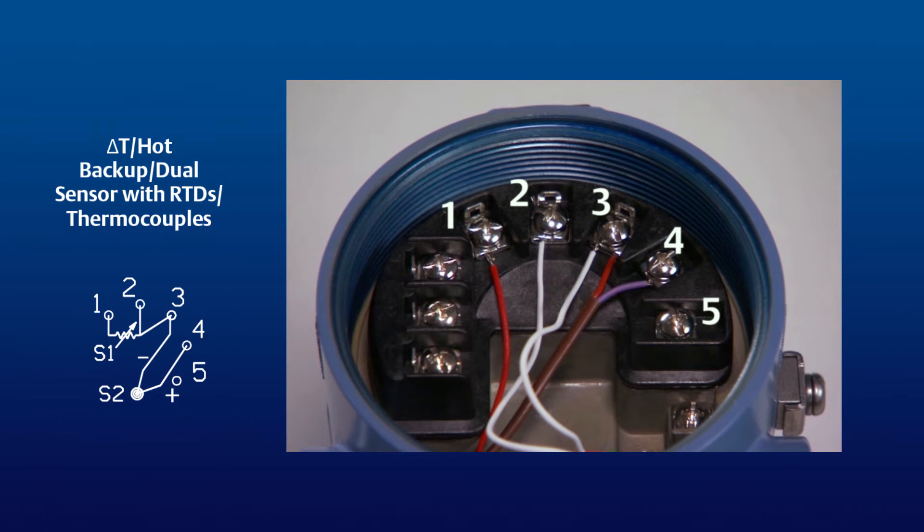Here is the proper wiring configuration for a 3-wire RTD sensor and a thermocouple. Note that the single red wire from the RTD is connected to terminal 1, and the two white wires are attached to terminals 2 and 3. Then the negative wire from the thermocouple is also connected to terminal 3, with the positive wire connected to terminal 4.